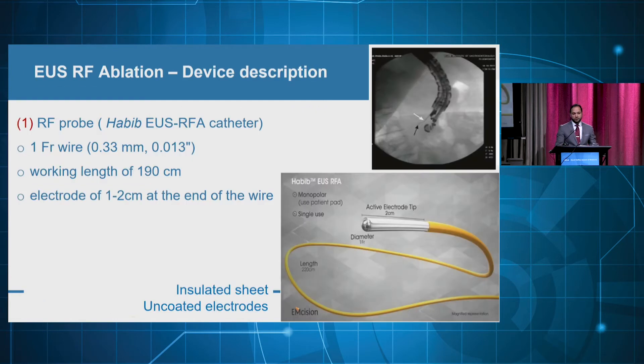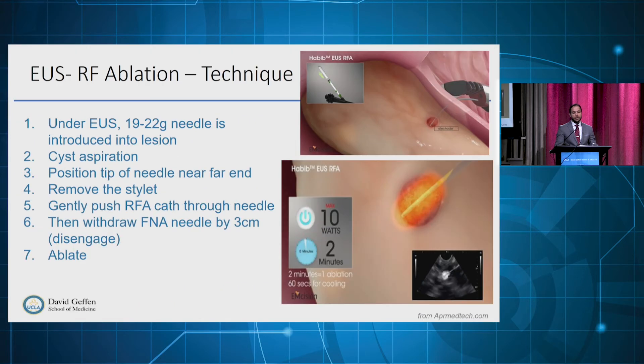There are a few devices available for EUS-guided RFA. The first is an EUS-RFA catheter that is very thin — one French in diameter. It has an insulated sheath and comes with 1 to 2 centimeter uncoated electrodes at the tip, which is the effective part. This catheter is used through FNA needles.